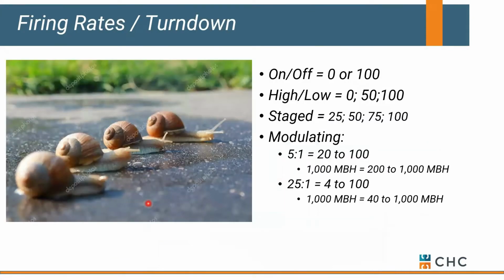Let's talk about firing rates, and that'll run us into turn down here in just a minute. An old school boiler might be on or off. It's either going 100% or it's sitting there idle. You might have a minimum turn down or a low high setup where the burner might be running at 50% or 100, or it's off. So not a lot of flexibility there. You might have a staged setup where you've got multiple gas trains and you can just bring them on as needed based on your load. Okay, not ideal, but it does allow you some flexibility.